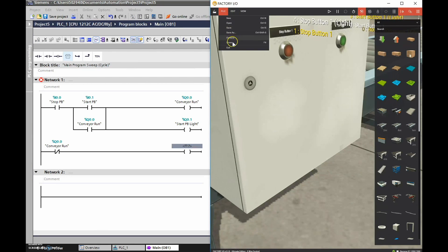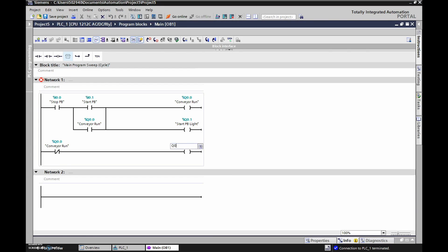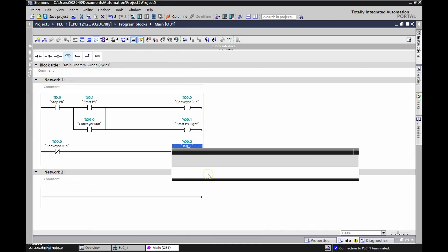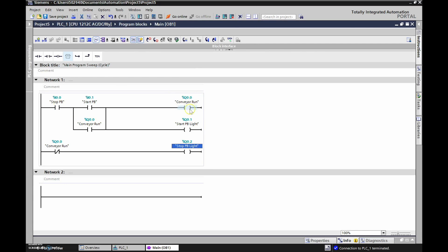The XIO looks for a zero in memory — meaning the output is off — so if the conveyor is off I'd like to turn on the stop push button light. We haven't added that output yet, so let's go to File > Drivers and add in another light. The stop button light is going to go to output 2. As soon as you do that it's part of your program — output 2, which is q0.2. Label it q0.2, right click and rename the tag to 'stop push button light'. There are other ways to do this, such as using a memory bit — if the memory bit is true turn on the conveyor and start light; if not, turn on the stop push button light.